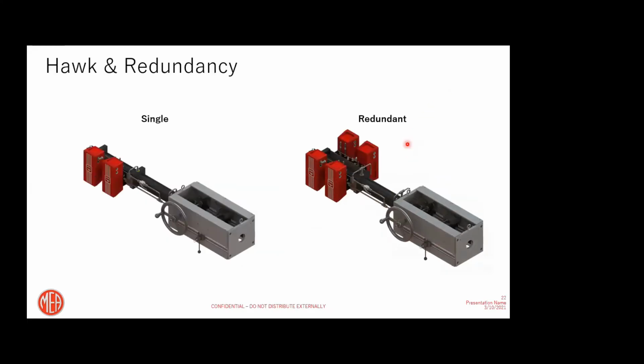So let's now talk about redundancy. We talked about our HPCUs and how we still didn't meet full redundancy without our main manifold being redundant. Here, even with a single unit, remember, one we use for precise positioning and another we use for speed. If one of these modules fails, the other one will still operate, but the unit just becomes slower.